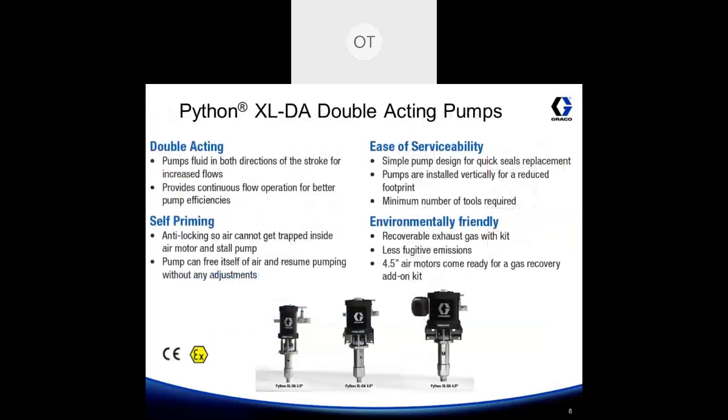Next let's take a look at the Python XL DA, or the double acting pumps. These pumps utilize the same Merkur air motor used on the Python XL, except they are mated with a double acting pump lower. The double acting pump lower pumps fluid or chemical in both directions of the stroke, doubling your flow when compared to a single acting pump. It's also utilized for providing continuous flow operation for better pump efficiencies. The pump lowers are also self-priming, so you don't physically need to be present at the pump to prime it, and in the event that you get any air trapped in the pump, it will automatically purge itself. We make it very easy to service with minimal tools required, and these pumps are environmentally friendly. On the four and a half inch air motor options, there is an available gas recovery add-on kit that you can purchase.